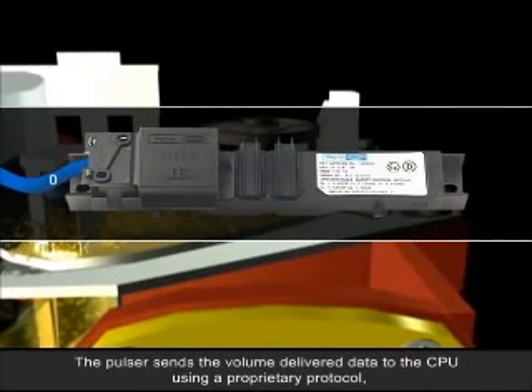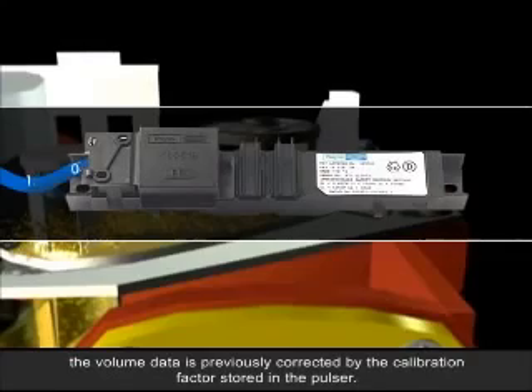The pulser sends the volume delivered data to the CPU using a proprietary protocol. The volume data is previously corrected by the calibration factor stored in the pulser.